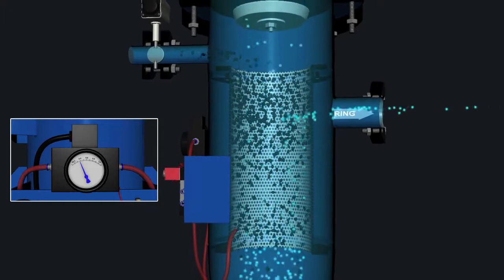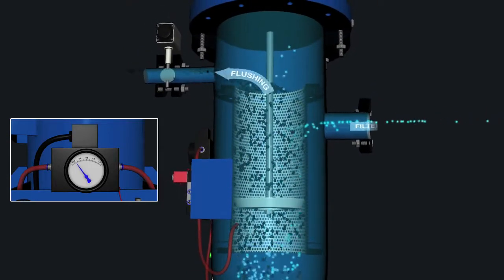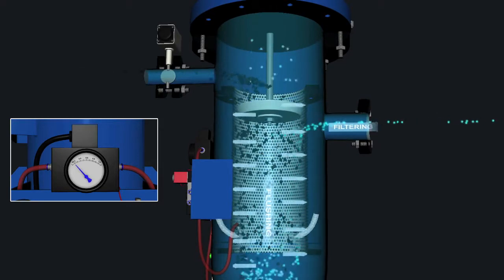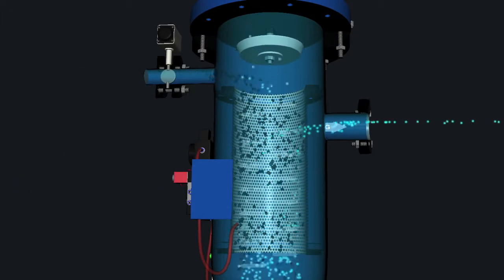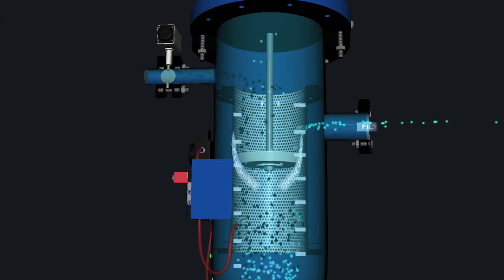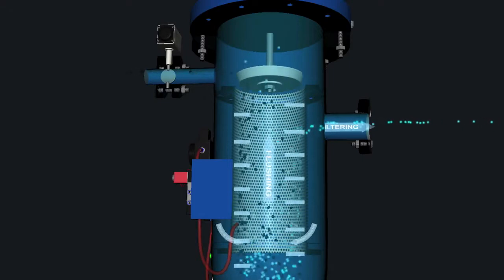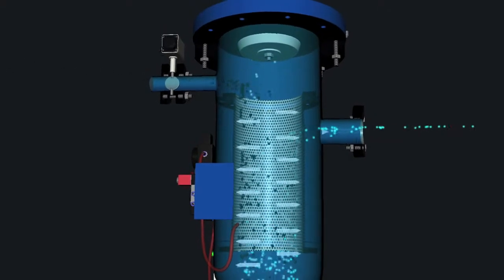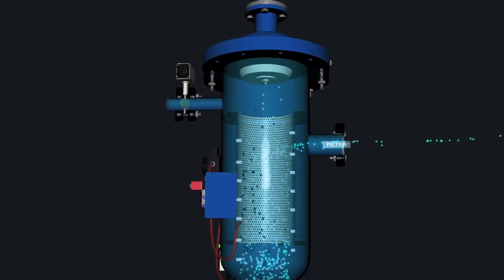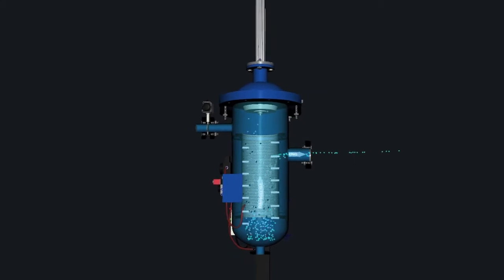After a short interval, a pneumatically driven piston fitted with a sweeping disc in a closed filter chamber is moved up and down. This action creates low pressure high velocity and high pressure low velocity zones near filter screen walls. As a result, flow reversal takes place, dislodging the clogged impurities from the filter screens. Once the piston completes the cleaning cycle, the drain valve is automatically closed and the filter resumes the next cycle.